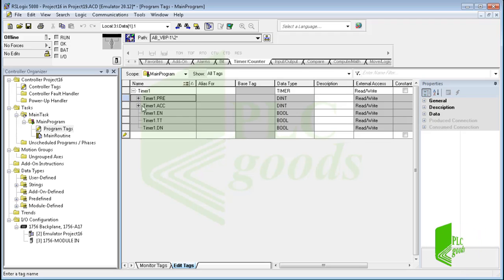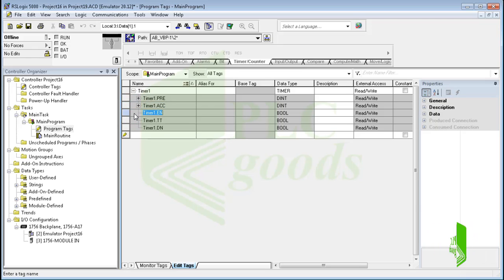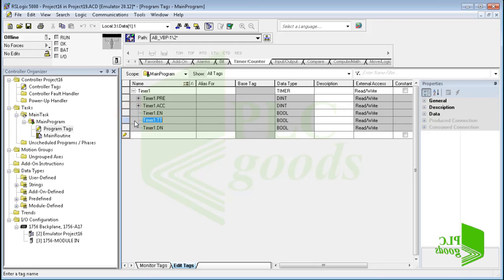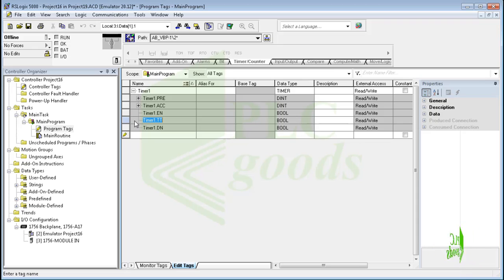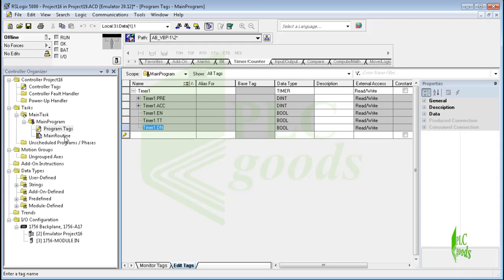The accumulated value shows the current time if the timer has been activated, otherwise it will be 0. The enable bit EN, whose type is boolean, indicates the timer instruction is enabled — this bit is true when the rung input logic is true and false when the rung input logic is false. The timer timing bit TT indicates that a timing operation is in process; this bit is true only when the accumulator is incrementing and remains true until the accumulator reaches the preset value or the timer is disabled. The done bit DN indicates that the accumulated value is equal to the preset value.